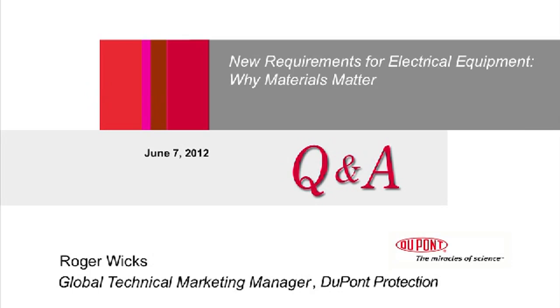Thank you, Roger. Here's a question. How do you balance aging time with aging temperature so that you do not cross the thermal breakdown barrier or exceed thermal stress capabilities? Yeah, that's a challenge, especially if one considers aging of combined materials. If you're looking at aging of separate materials, like a Nomex paper or a polyester film by themselves, you usually have an understanding of their thermal capability. For example, when we aged Nomex paper, we aged it at temperatures ranging from 260 C to 320 C to get a 220 C rating.